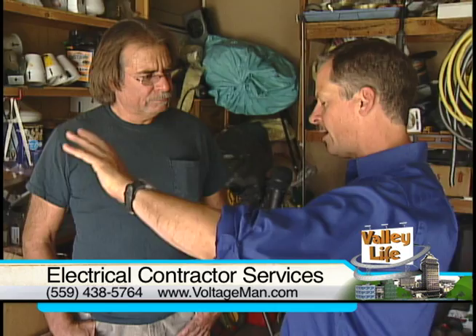All right. Now, that happens to me a lot, too. And I go out and I've got to flip it, but I never really get to the root of the problem. Or maybe I've got too much stuff plugged into one of those strip outlets, but there's a couple other reasons why that could be happening. So give me kind of a rundown of the main things you see. Well, the main thing that I see is obviously overloading the breakers, putting too much amperage in on a 15 amp circuit, usually in the bathrooms with hair dryers.